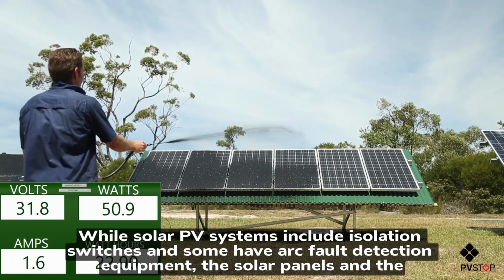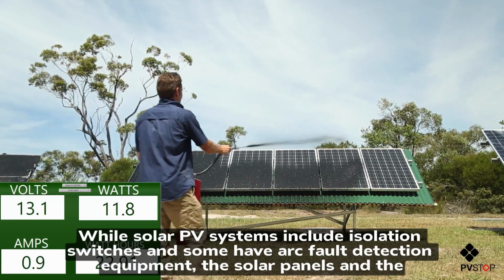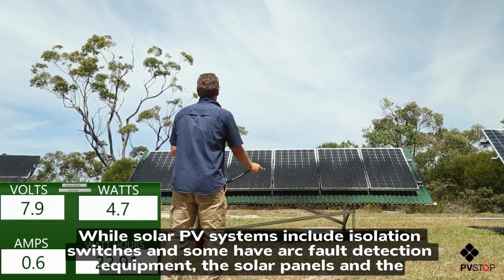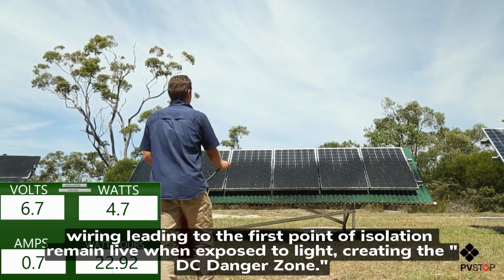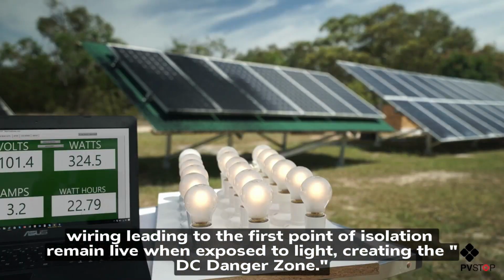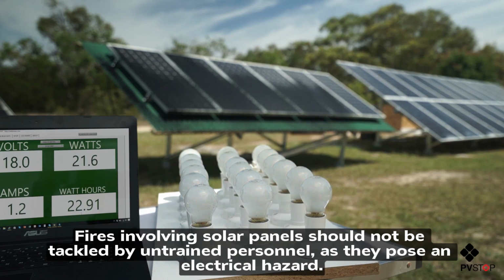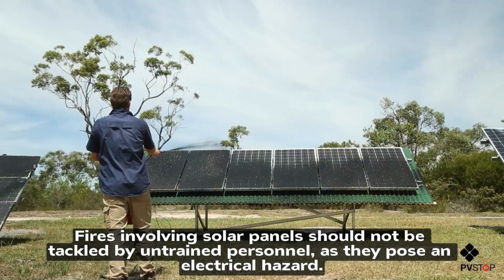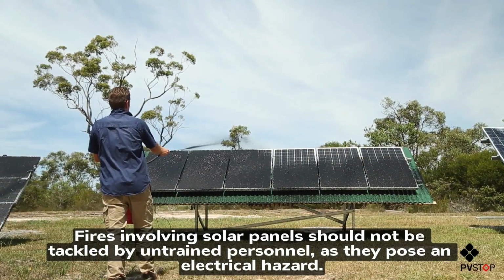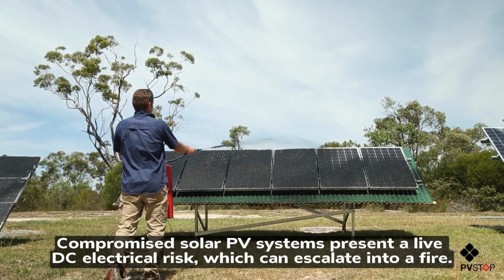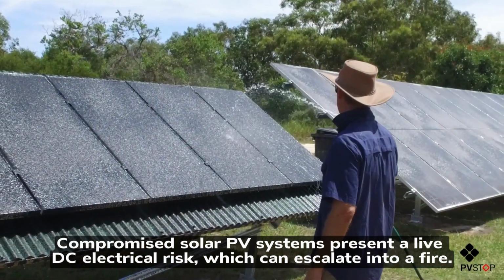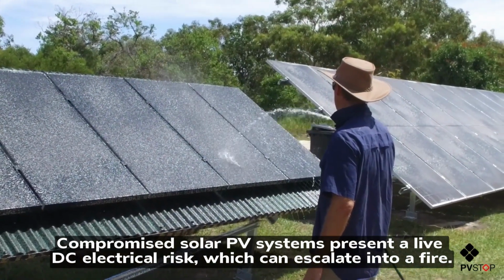While solar PV systems include isolation switches and some have arc fault detection equipment, the solar panels and the wiring leading to the first point of isolation remain live when exposed to light, creating the DC danger zone. Fires involving solar panels should not be tackled by untrained personnel, as they pose an electrical hazard. Compromised solar PV systems present a live DC electrical risk, which can escalate into a fire.